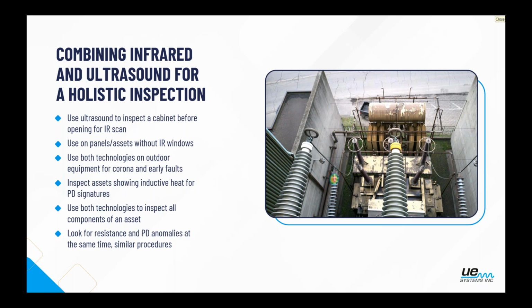Looking for outdoor equipment, once again, looking for that corona. If we're outside inspecting a substation with infrared, I would pull ultrasound out to look for that corona event that might be happening, as well as very early stage faults that, due to solar loading and other factors, might be very hard to detect with an infrared camera. I'd look for both technologies together to be used during inspection for inductive heating issues with partial discharge.